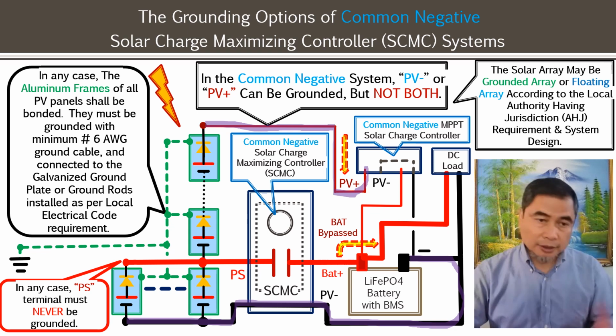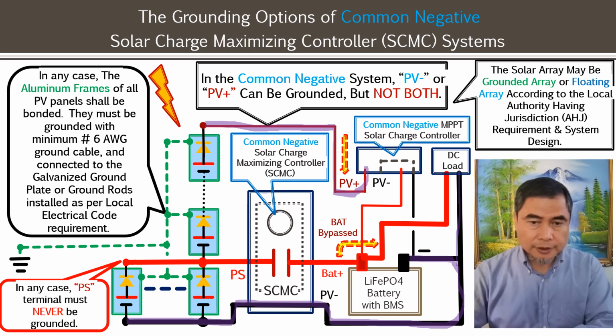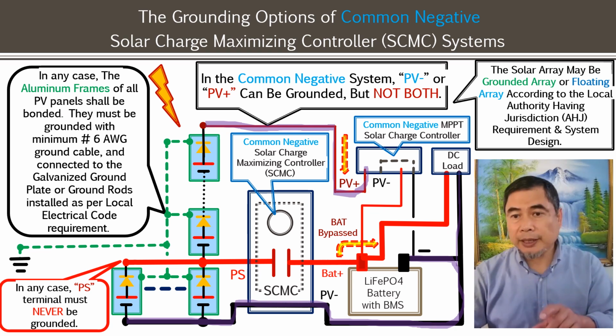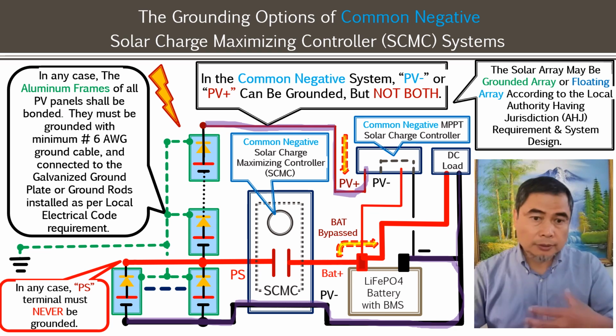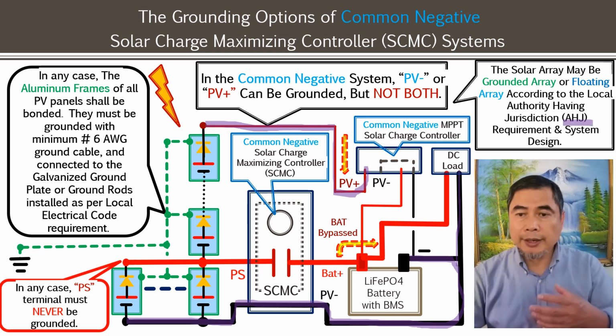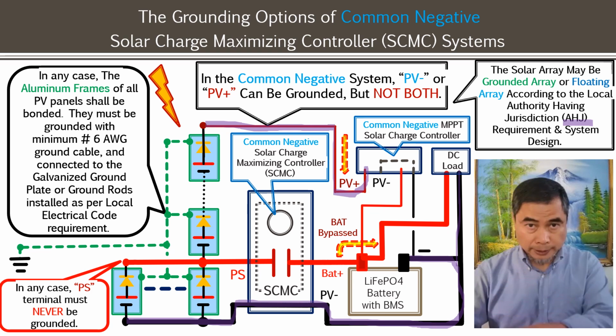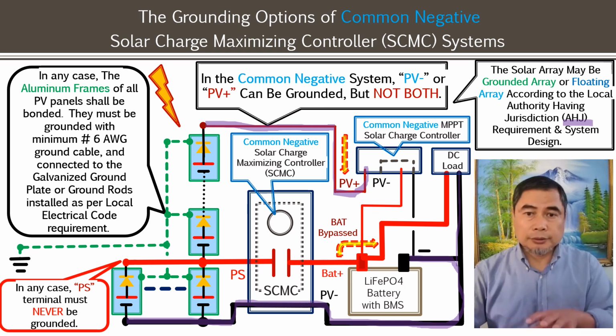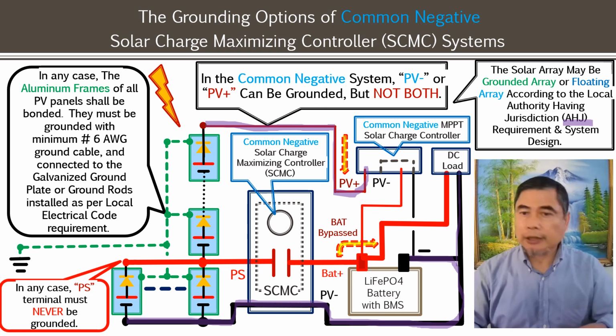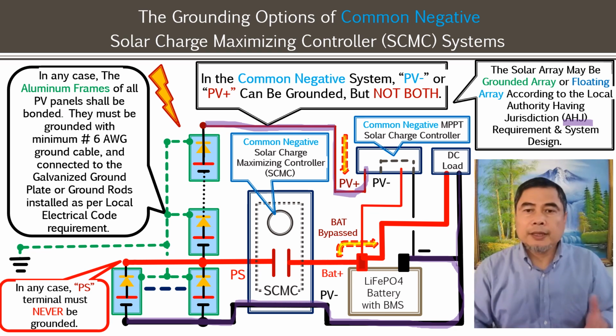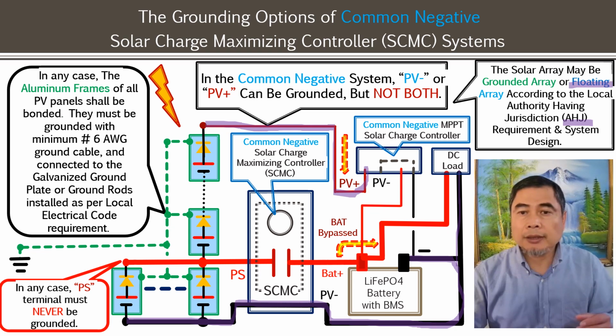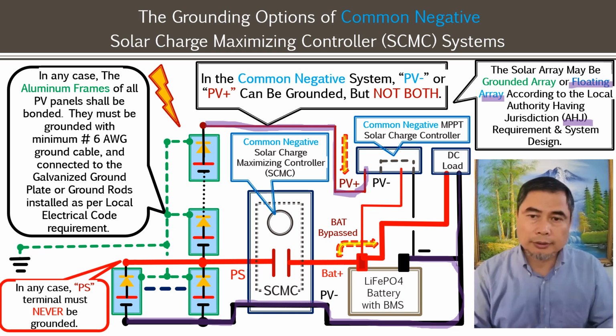A PV negative in the common negative system design is also battery negative. You could have the negative connected to the ground, or you could have the PV positive connected to the ground. It all depends on the electrical code, the local electrical code, or what you call the local authority having jurisdiction, AHJ. Based on that design, you determine which to connect to ground, or you can just leave it floating. We do have some floating arrays, where none of them is actually connected to the ground.